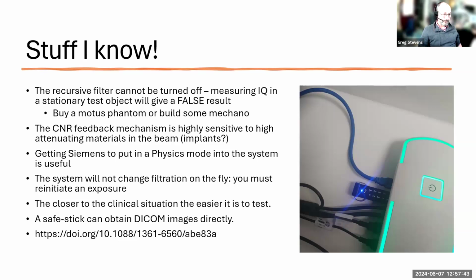The CNR feedback mechanism is quite highly sensitive, as Charlotte mentioned, to high attenuating materials. And I suspect that the system is inherently unstable, so it just moves around the equilibrium level. When you put in something like a high attenuating material, that movement becomes quite chaotic. I'd recommend getting Siemens to put in a physics testing mode. We've got a physics testing mode which just stops the removal of copper.